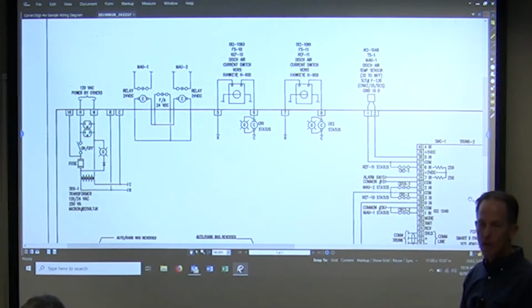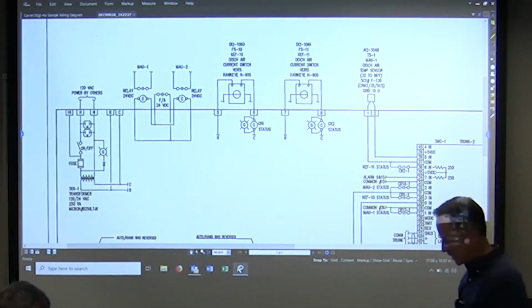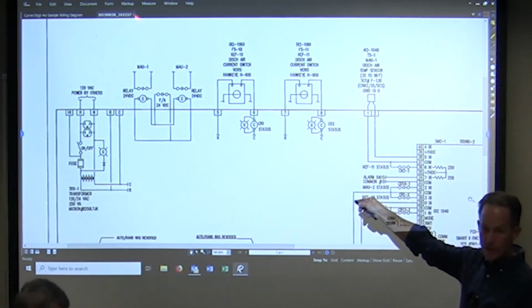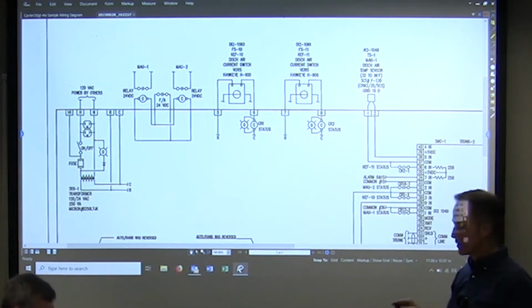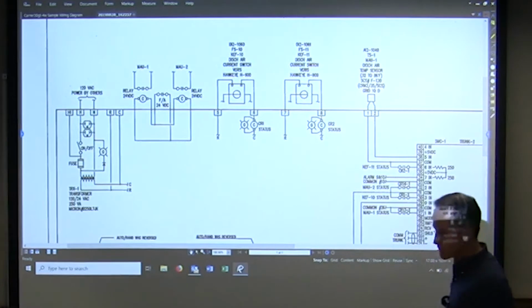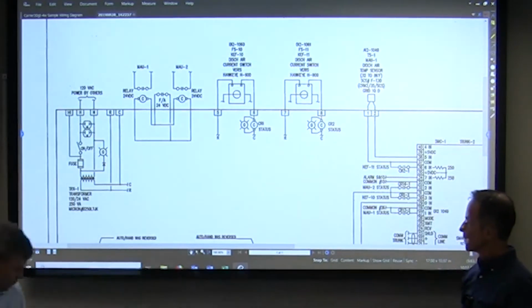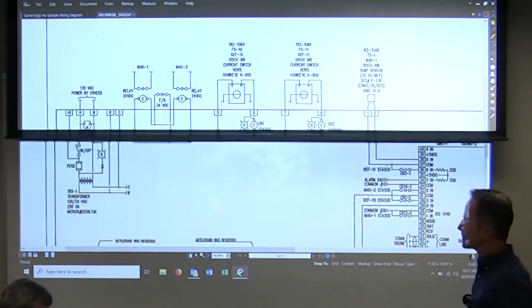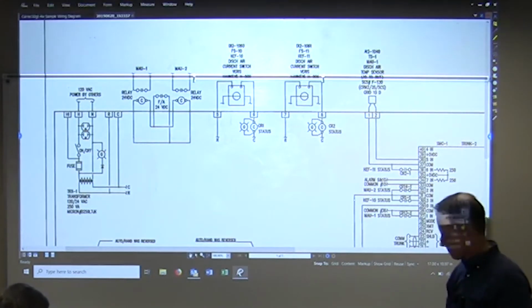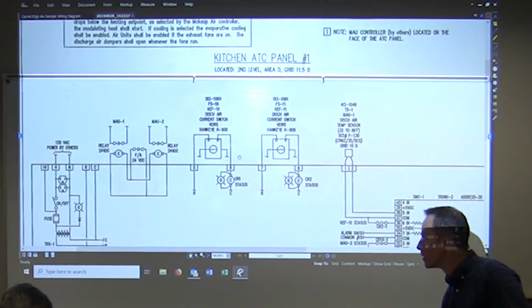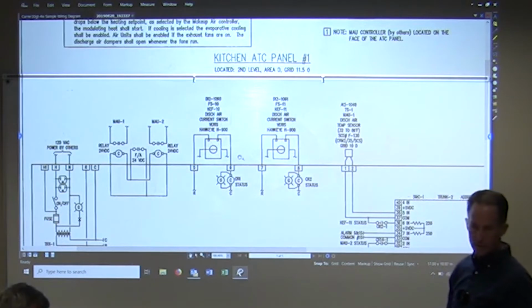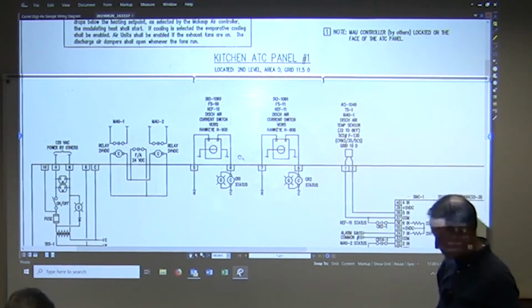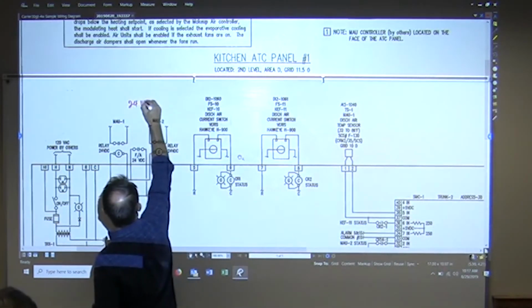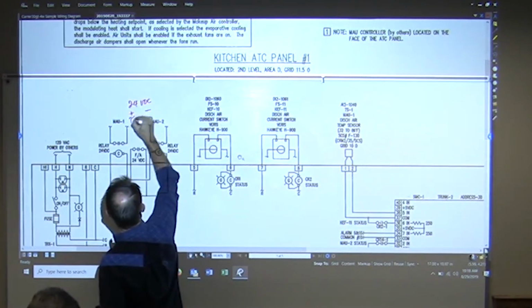Okay, so there's two ways that we can fix this. One is if the fire alarm system is 24 volts DC, and I can get to that 24 volts DC. So say up here, somewhere out here, I have 24 volts DC available. What would I have to do to fix this? Would you kick up our screen all the way? I apologize, this will be a little shiny for some of you. So how can I fix that? Anybody? Okay, so say I've got 24 volts DC plus and minus right there.